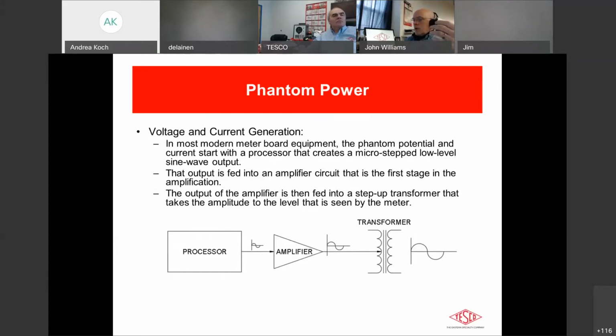Any modern meter test board will create the phantom power, both the potential and the current, using a couple of simple steps. Again, simple in concept, a little bit more difficult in execution, but basically it starts with a processor of some sort that produces a sine wave. With the types of processors that we have nowadays and the accuracies and speeds, we can create really, really accurate sine waves using digital electronics. Once that sine wave is produced, that's the basis from which you're going to generate your power. That's pushed out to an amplifier board, which does exactly what it says. It increases the amplitude of the signal that's riding on that sine wave.